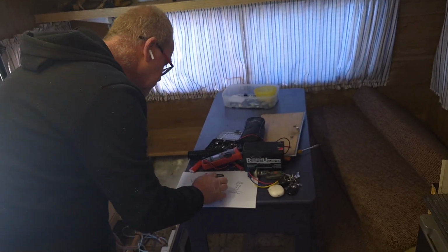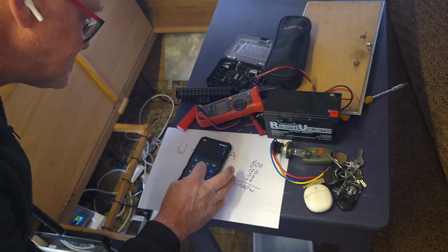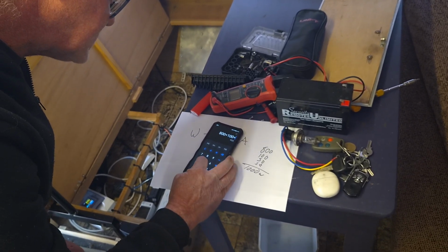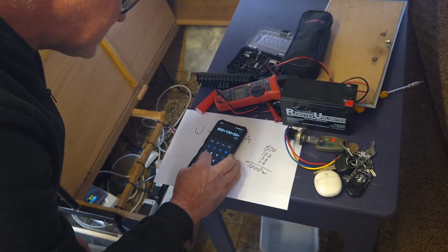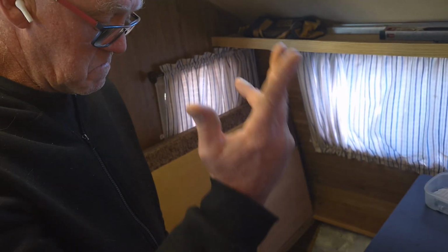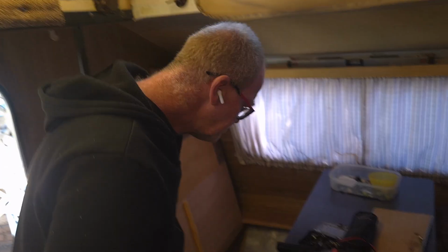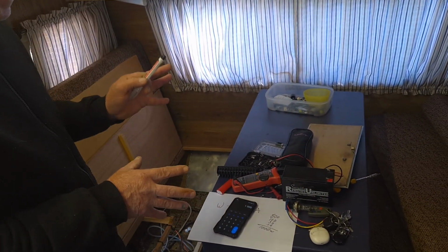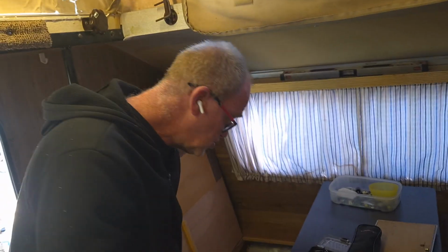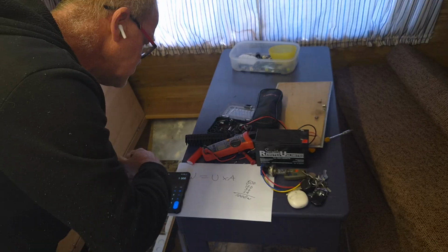1,000 watts, which is at 230 volts. So we nip over to the calculator and we add them up. 800 plus 100 plus 50 plus 50 gives us 1,000. Simple. So I can get a 3,000 watt, 2,000 watt inverter, whatever inverter I get, I'm going to be good with that. But these are all running at the same time. We'll get into that. Quick calculation at 230 volts, because watts is 1,000.